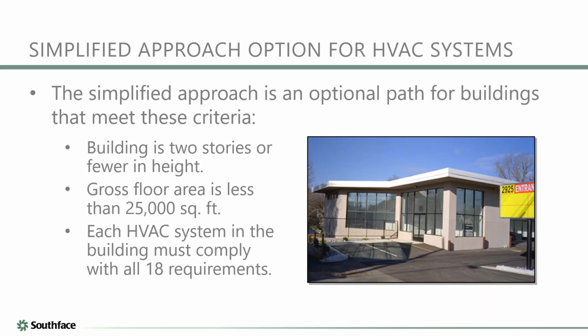So what this does is take something that could be extremely complicated, the commercial section of the Energy Code, and try to make a simplified version of it that actually applies to a large number of the buildings that are being constructed in the real world. And hopefully in doing that, it makes the code easier to both design around and easier to construct and inspect for in the real world. And in doing so, we hope that that increases overall compliance with the code by making the code requirements understandable and straightforward, and by making them easy to inspect for. And so the vast majority of commercial buildings pulled are likely to fit this small building profile of 2 stories or less and 25,000 square feet or less, and be able to use this compliance pathway for mechanical systems, which is located in ASHRAE 90.1.